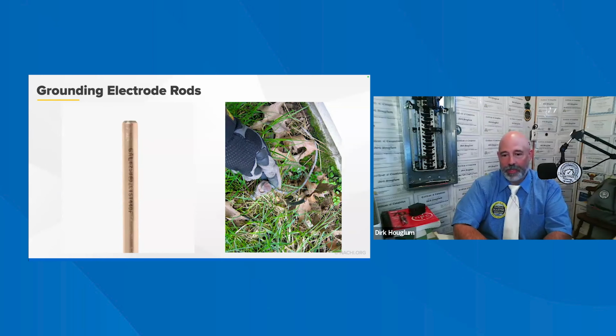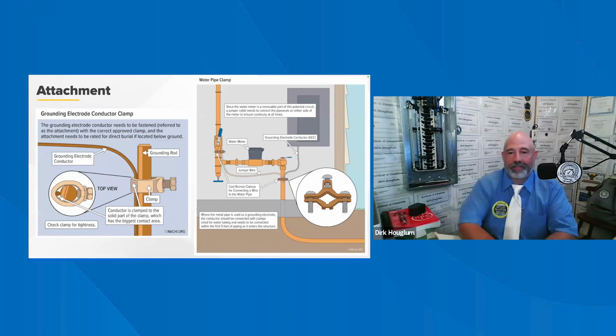In the image, the home inspector is looking at the upper end of the driven rod and its attachment. Pipe or conduit made of steel shall have an outer surface that is galvanized or otherwise metal coated to resist corrosion. If the material is iron or steel, the electrode must have its outer surface galvanized or metal coated for corrosion protection. Good to know, isn't it?